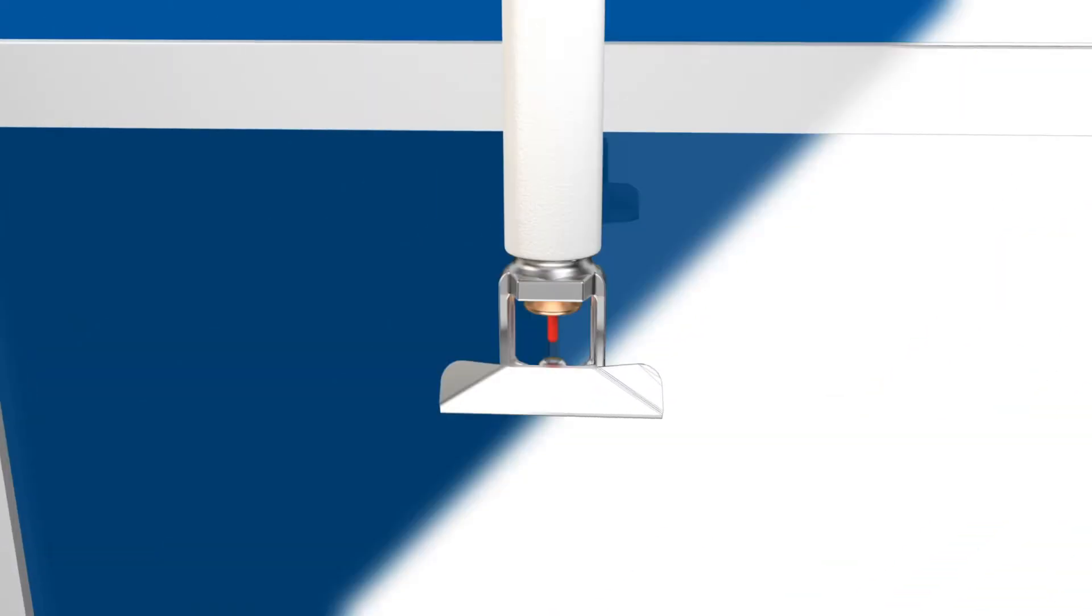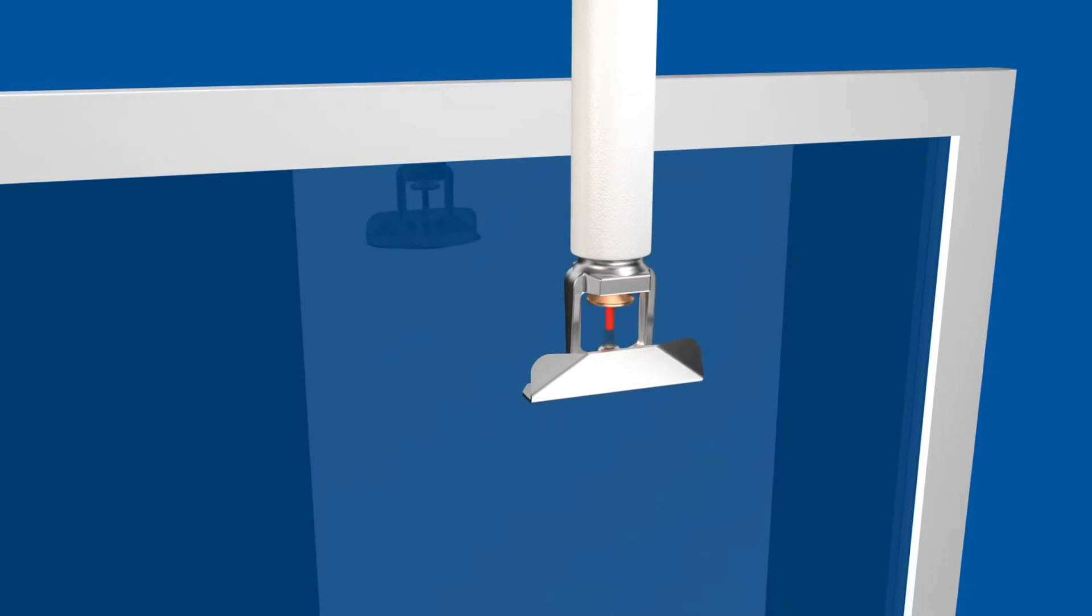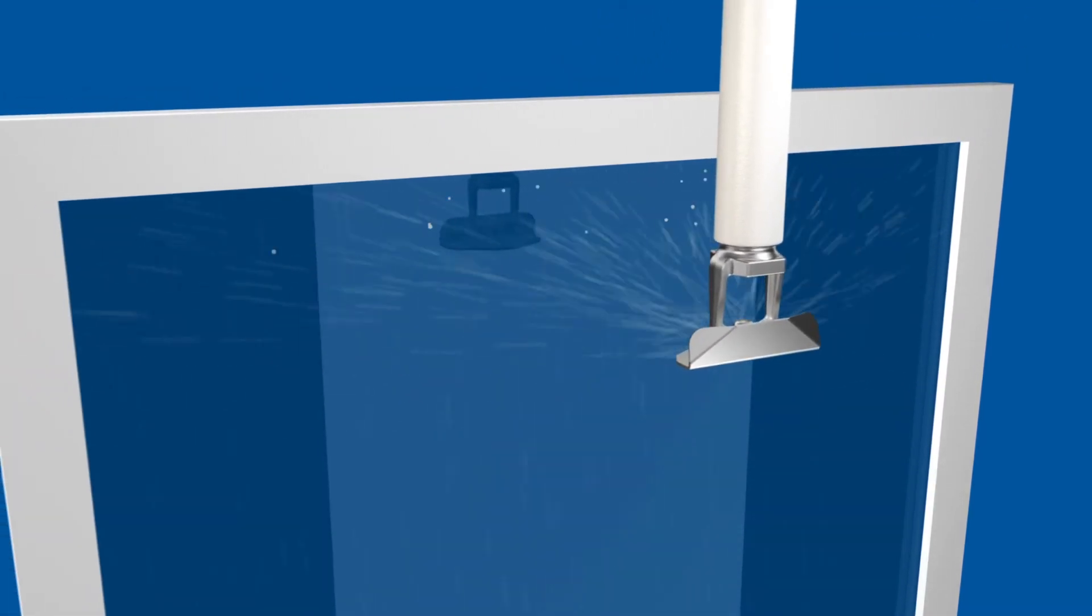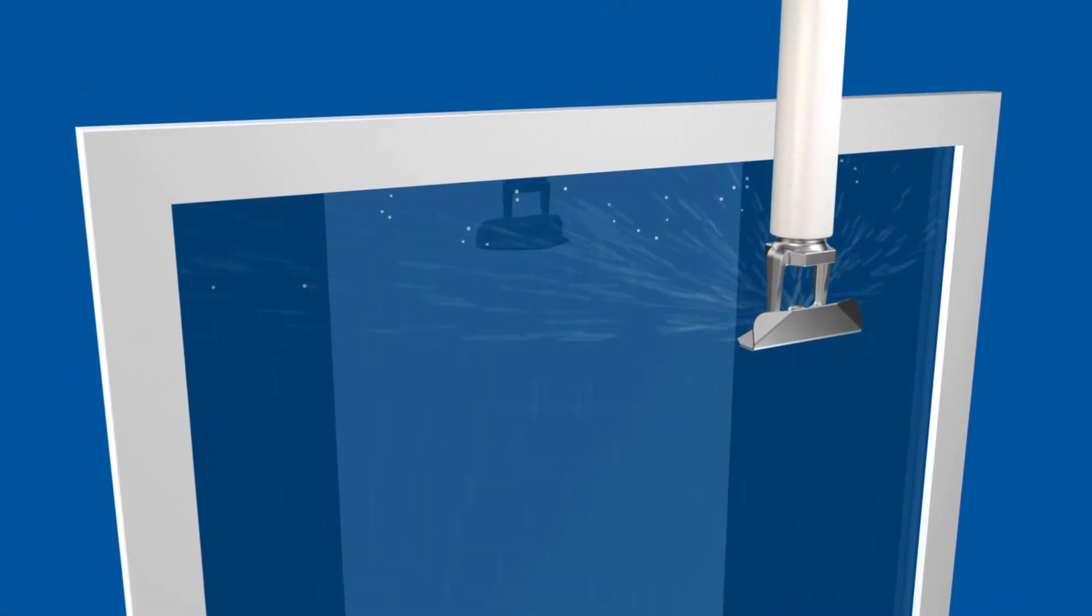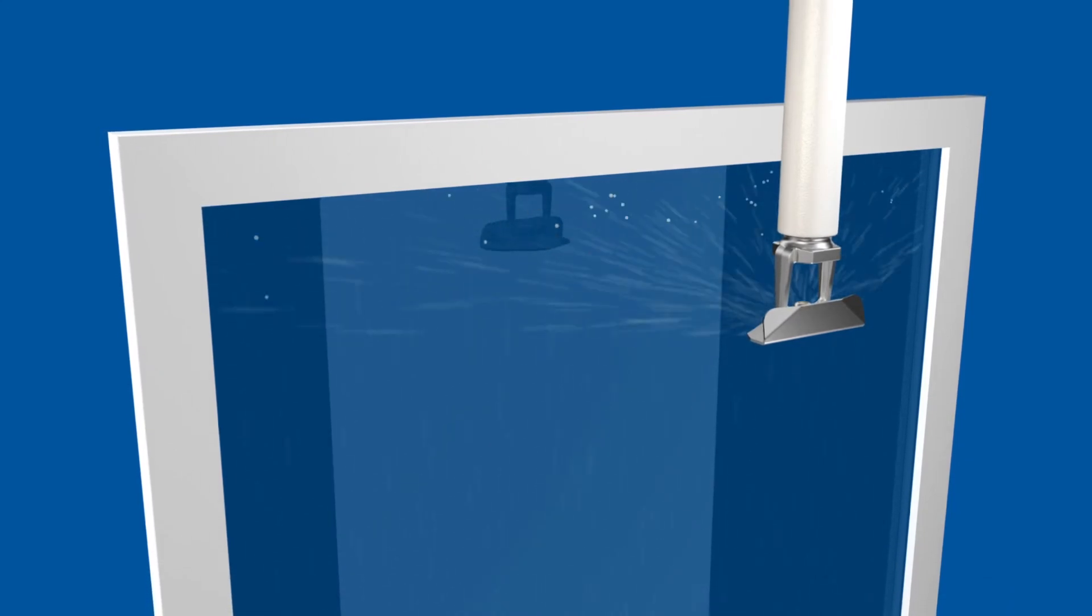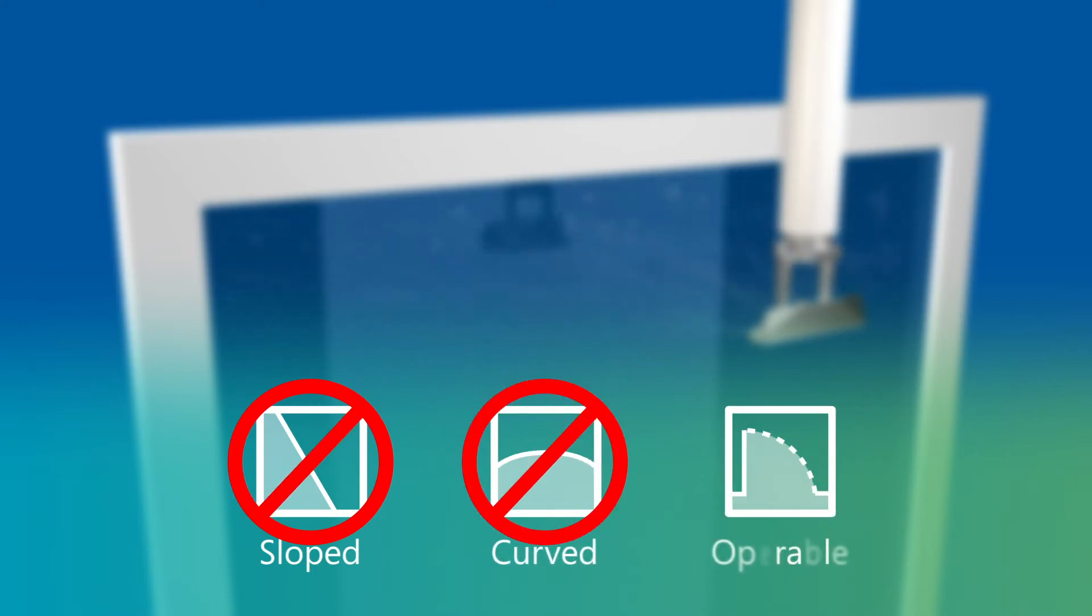Window sprinklers are designed to provide full protection for the entire window. The spray pattern wets the full pane of glass from corner to corner, leaving nothing dry. The sprinkler is designed for flat surfaces and typically is not used on sloped, curved, or operable glass.